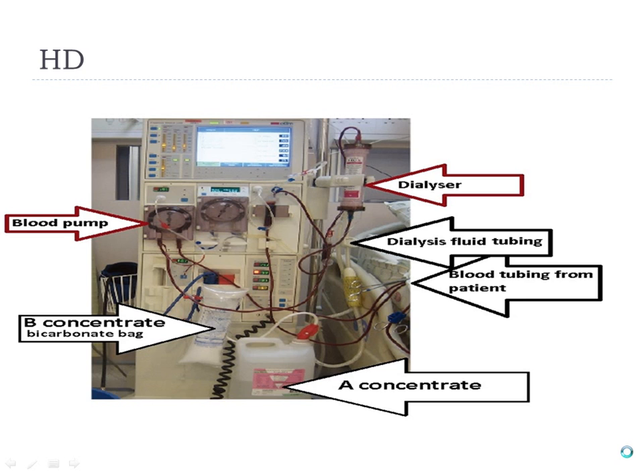Here is a dialysis machine. The concentrate is the dialysate — the solution that bathes the dialyzer, which is the kidney. Blood tubing comes from the patient, pulls blood to the machine, goes through all the pumps and through the dialyzer, then returns to the patient.